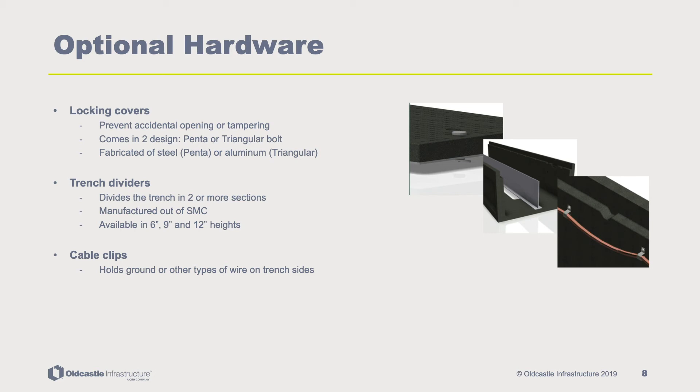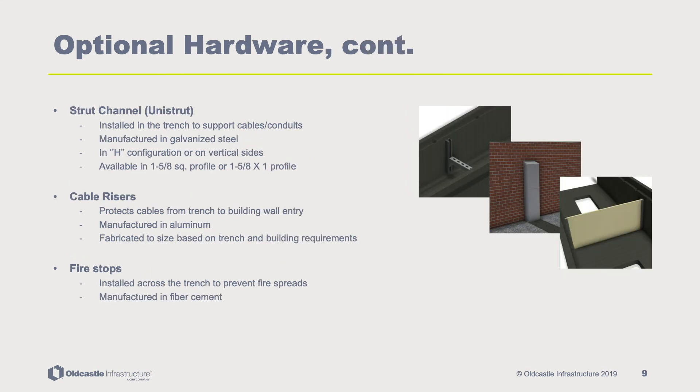Cable clips hold ground or other types of wire to the sides of the trench. Strut channel, also known as Unistrut, is steel manufactured and installed in the trench to support cables in an "H" configuration or on the vertical sides of the channel. Cable risers are aluminum made and protect cables from trench to building wall entry; they can be fabricated to length, width, and depth as required. Firestops, made from fibro cement, can be installed across the trench to prevent fire spread.